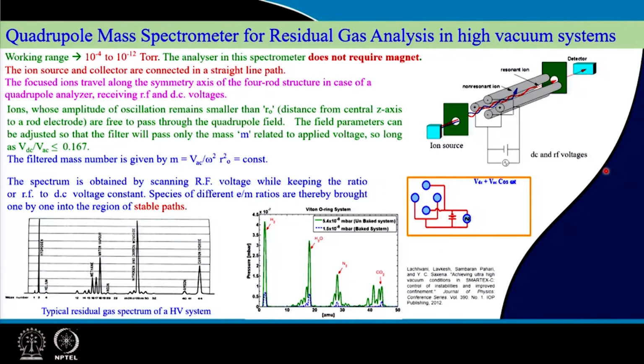But things are little more easier when it is quadrupole mass spectrometry. Analysis is difficult, but it is easy because here no magnetic fields are there, magnets in the vacuum chamber are not good also sometimes, but of course magnetic fields can be applied. Making it in line with the gas particles flow via detector will be little difficult, and this purpose is for helium detectors mostly. This is a high sensitive detector. Quadrupole mass spectrometers' purpose is residual gas analysis, but locking it you can use it for leak detector, sensitivity will be less. That is what we will discuss in the next slide.